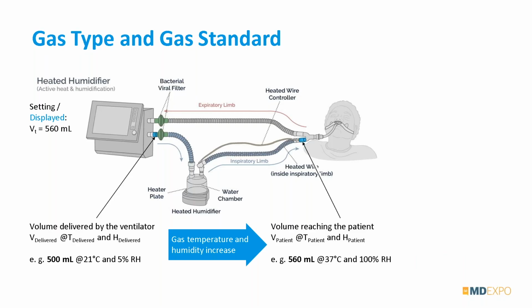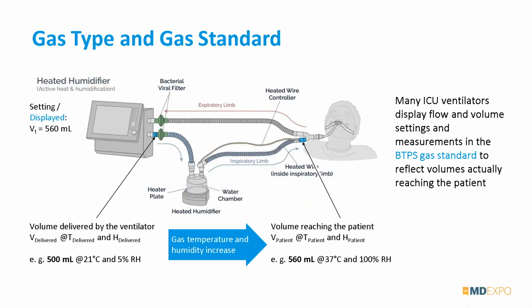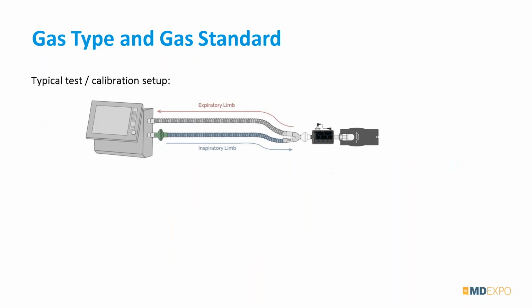When in reality, that ventilator sends only 500 and expects the conditions to be changed by the humidifier, and then the volume changes. So we call body temperature and 100% relative humidity BTPS, body temperature pressure saturated. And that is another gas standard that we just talked about. Well, what happens to us as technicians or engineers when we want to test that ventilator? Has anybody ever tested a ventilator with a humidifier in the circuit? It doesn't happen, right? It's really hard on your test equipment when you do that. So we're going to be testing with just a plain circuit.